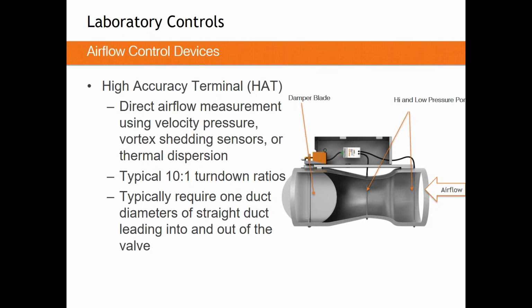What we do here is we compress airflow down through that Venturi section. That speeds the air up and creates a pressure drop between that pressure port in the front and the pressure port in the neck of the valve. Now the pressure drop that we're going to see there is orders of magnitude larger than what a VAV box will see. So if a VAV box is measuring about a 1/10 of an inch of pressure drop to achieve its full flow between those two ports, we're going to see almost 2 inches of pressure drop that we're able to measure using a slightly better transducer.